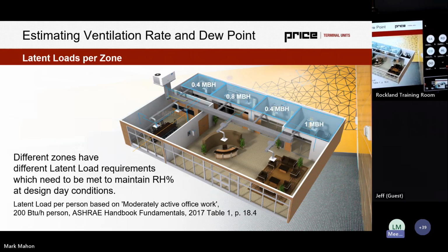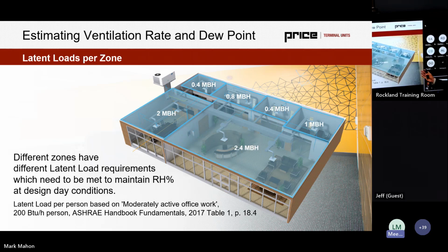And in this case, with it being an office, I didn't actually perform load calculations for all these zones. I just wrote it all out and dreamt it all up. So my assumption in this case is 200 BTUs per hour per person, which is from ASHRAE Handbook of Fundamentals, based off of moderately active office work. I looked at the square footage of each zone, looked at the ASHRAE 62.1 assumption for how many people we're going to have in each zone, and that's how I came up with the latent loads. So we need this much latent cooling provided to each zone on design day.